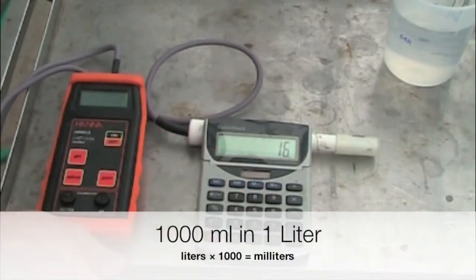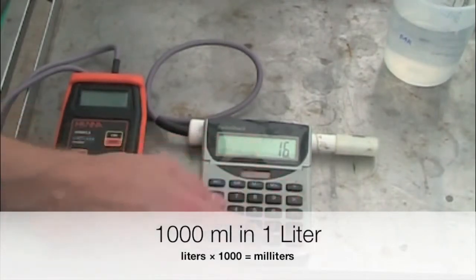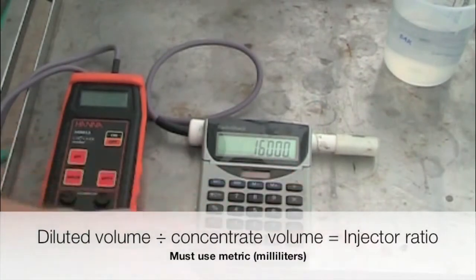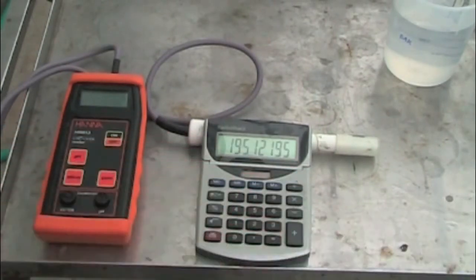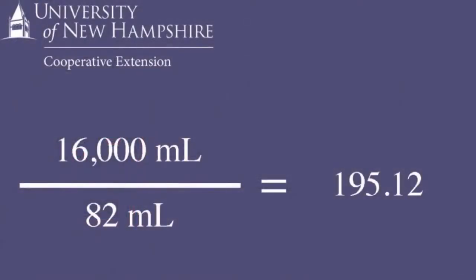We now need to use our calculator. The calculation has to be done in milliliters, so we need to convert 16 liters into milliliters by multiplying by 1,000 to get 16,000 milliliters. Then divide 16,000 by 82, the number of milliliters of concentrate it took to get 16 liters of solution. To show this again, we divided 16,000 by 82 to give us a little over 195. We anticipated our injector to be set at 1 to 200. This tells us that it is actually set at 1 to 195. For most cases, if we are within 1 to 2%, we are okay. And in this instance, we're within that range.